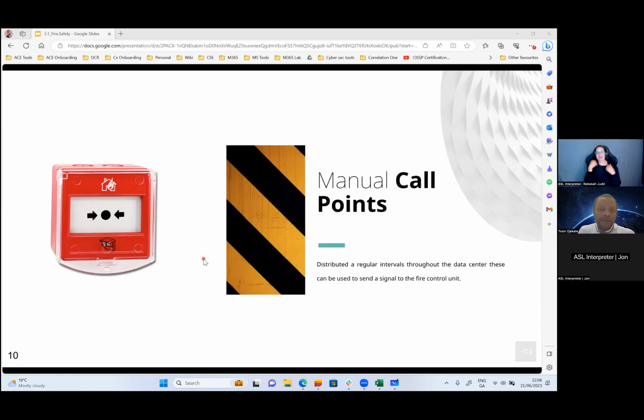Sometimes when there's a fire in a multi-level floor, it's difficult to know immediately where the fire starts from. I've been in a building where for the first 10-15 minutes, nobody was sure where the fire alarm was triggered from. Everybody was confused, not knowing whether to use the staircase, which staircase, whether to come downstairs or remain where they are. That's why it's important to have a situation room monitoring this, since most of these devices have sensors reporting.